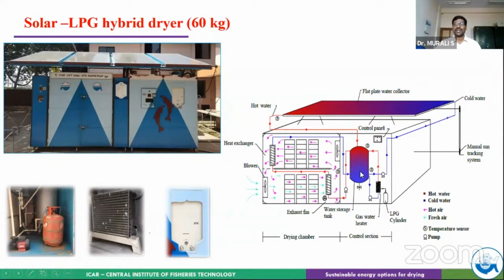This is called the solar pump connecting the bottom tank and the collector outlet. We also kept one more sensor to maintain the top temperature. This LPG system checks the top temperature; if it is only 70 and we have set it to 90, the LPG will work simultaneously, taking the cold water, heating it, and putting it at the top. Similarly, if the temperature of the drying chamber goes above 60 or 55, whatever we are setting, there is a temperature sensor that senses the inside temperature. Once it is attained, this sensor gives a signal so the pump is cut off.